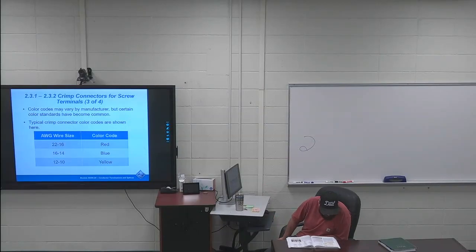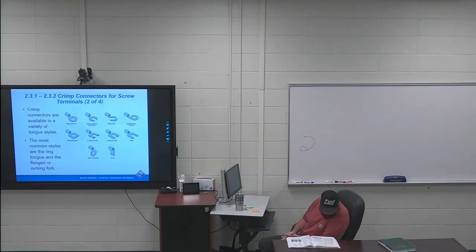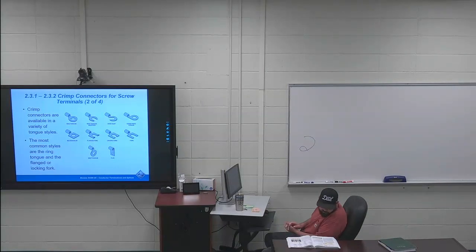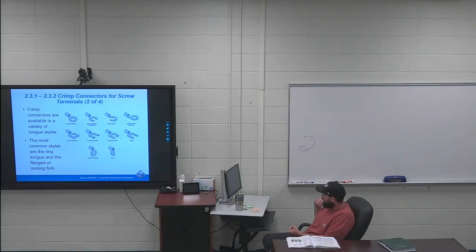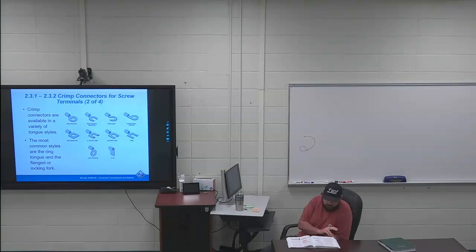Next paragraph, right in the middle of that paragraph, I've got three sentences highlighted: tongue styles vary depending on termination requirements. Figure 30, which is what's on the board, shows standard tongue styles. The styles most frequently used are the ring tongue and the flange or locking fork. That just depends on what you're using. I've used the ring tongue, not a huge fan because you have to take the screw all the way out to get them in and out. I usually like the fork style the best. Locking fork, I haven't really used a ton, but it's just going to be whatever environment, whatever is available to you. You have a bunch of different options for that.